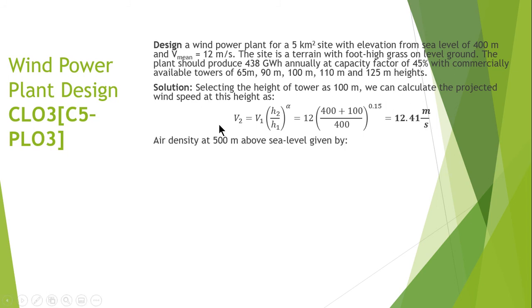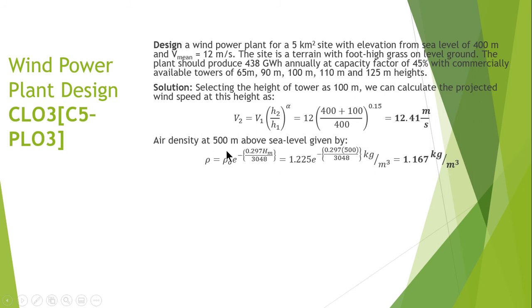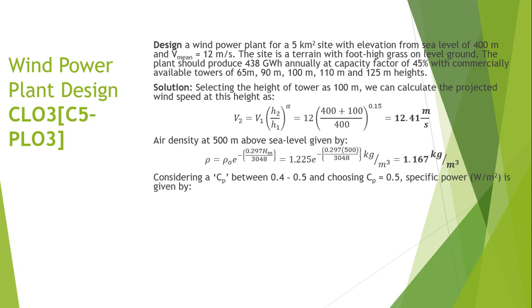Next, we calculate the air density at 500 meters above sea level. The formula is: density equals the sea-level density multiplied by e to the power of negative 0.297 times height in meters divided by 3048. Substituting h2 = 500 meters, the air density is calculated to be 1.167 kilograms per cubic meter.